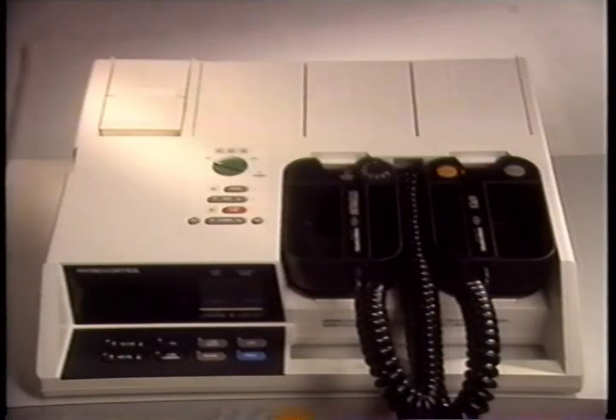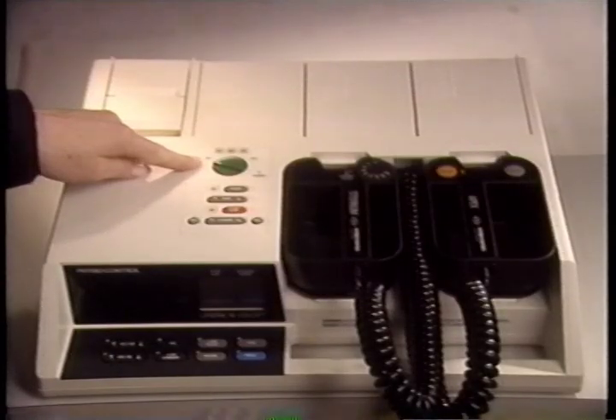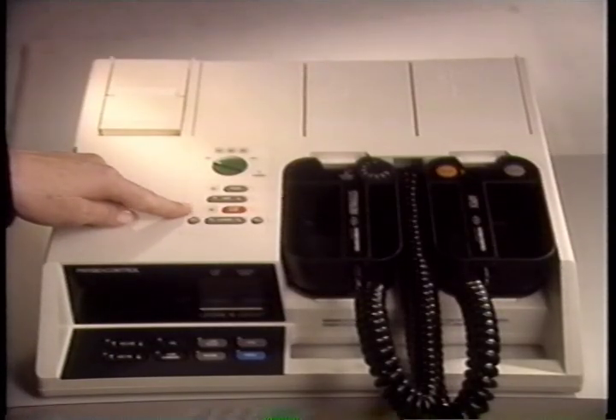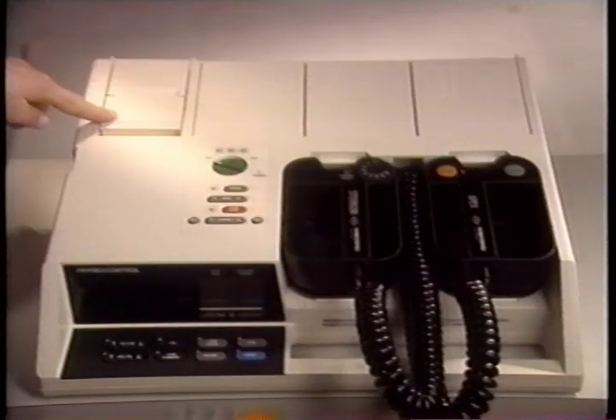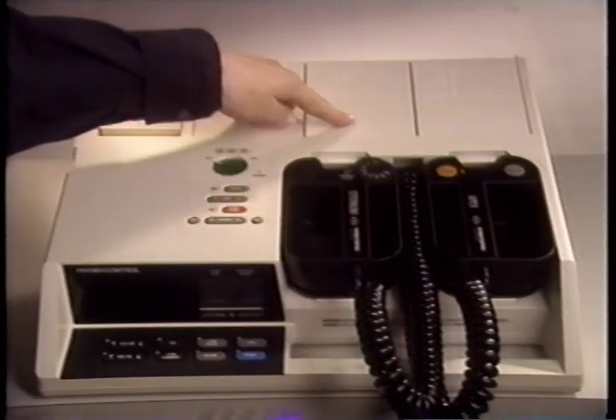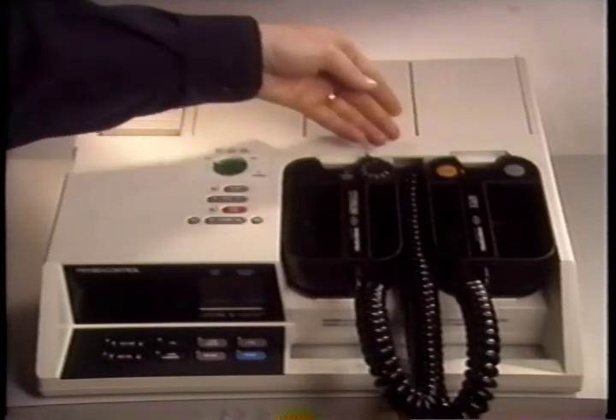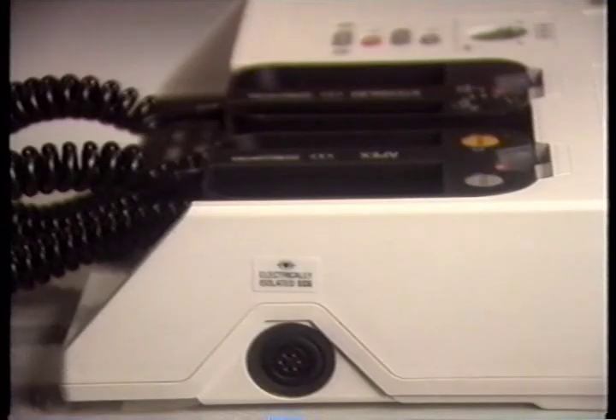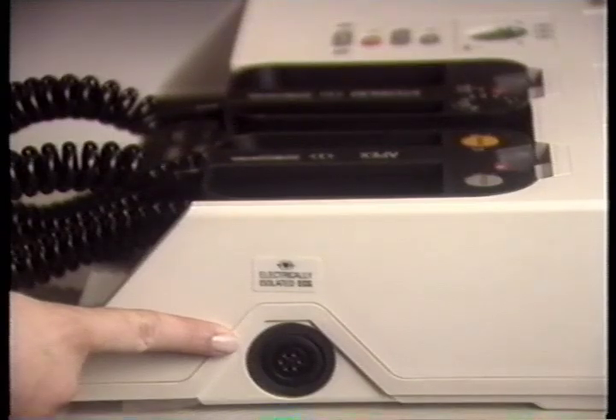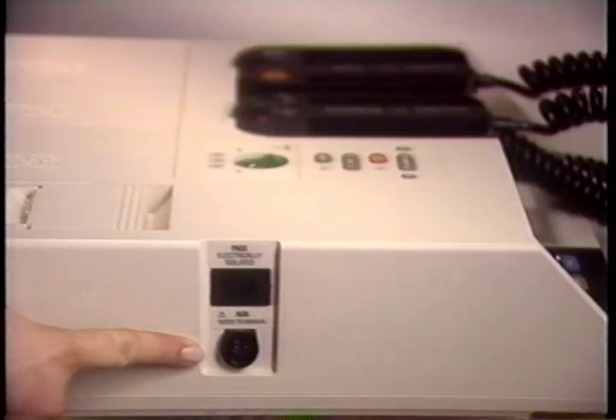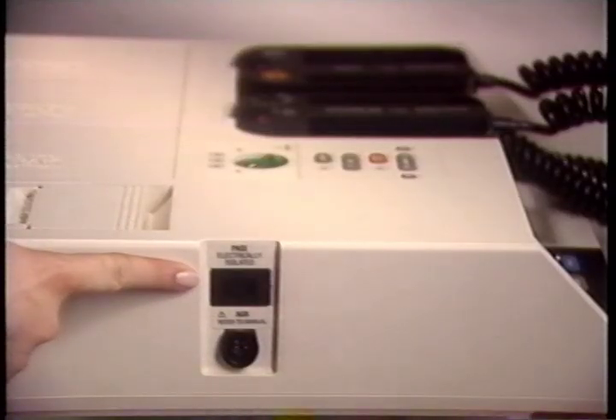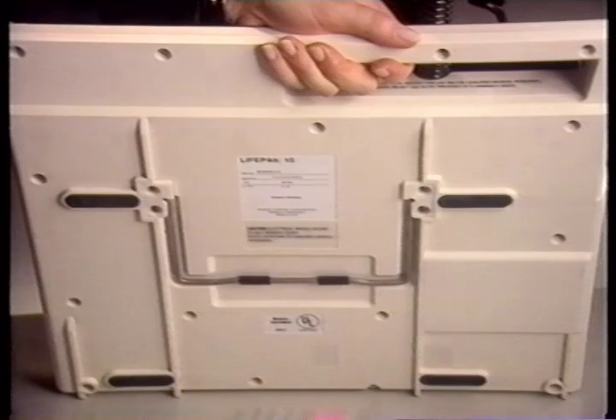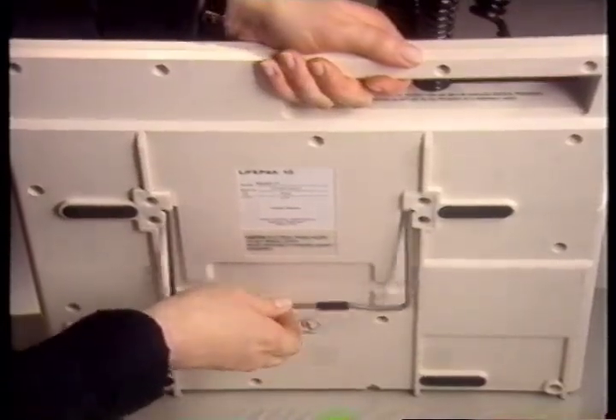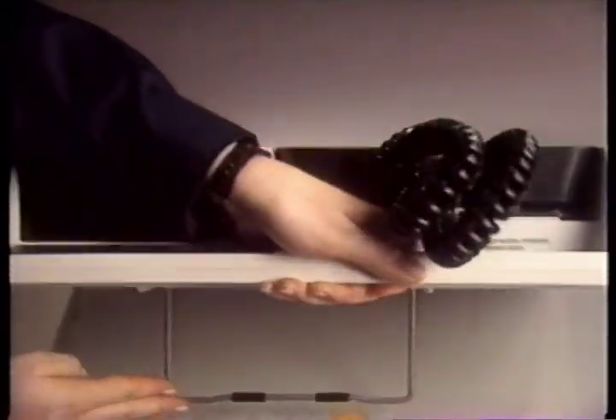Viewing the LIFEPAK 10 from above, you'll notice the main power switch, controls for the optional non-invasive pacer, strip chart recorder, 3 interchangeable LIFEPAK battery packs, and the defibrillator paddle controls. The side panel closest to the defibrillator paddles contains the ECG cable input connector. The opposite side panel houses the auxiliary connector and the non-invasive pacing cable connector. The bottom of the LIFEPAK 10 features an incline bail that can improve the viewing angle if the LIFEPAK 10 is placed below eye level.